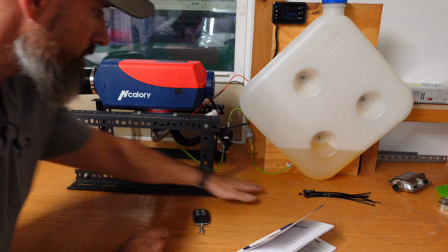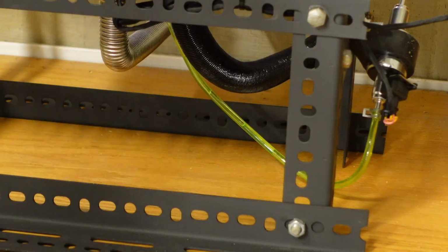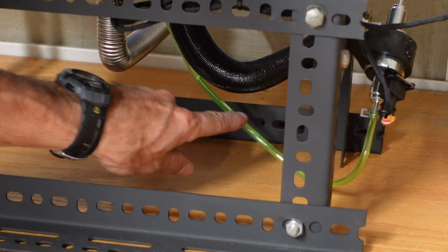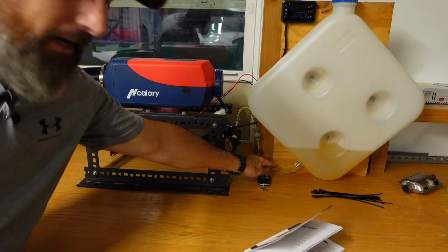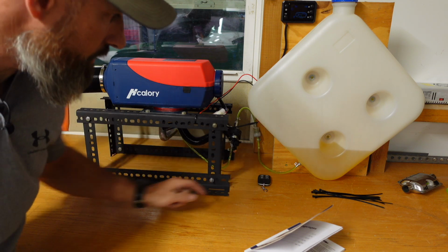I don't see any leaks. That's good. There is air blowing out of the end. When you look at the fuel lines, you'll see the fuel pumping through it. It's going to have to work all that air out. The longer your line, probably the longer this is going to take to light it up for the first time. Back here, right after the tank, it looks like there's no air in it.